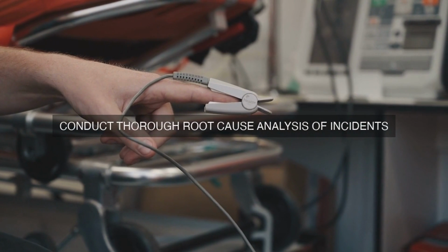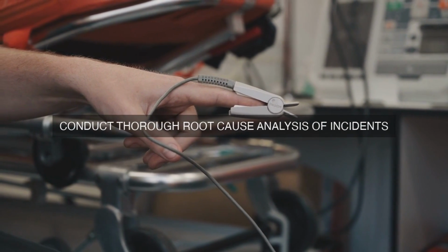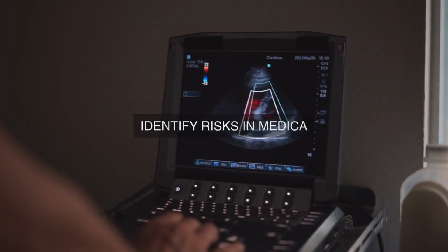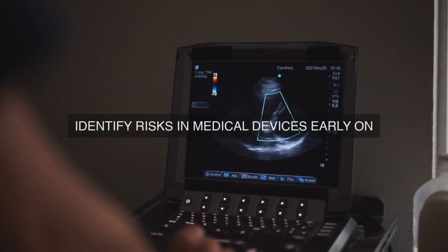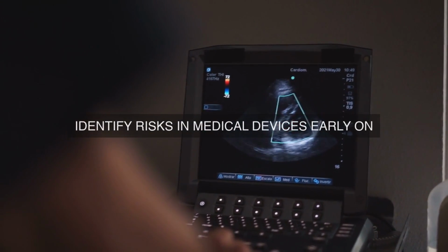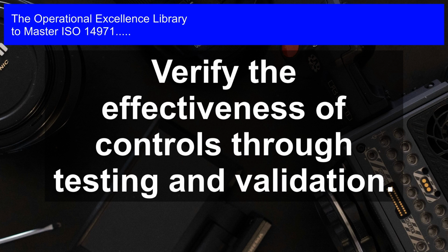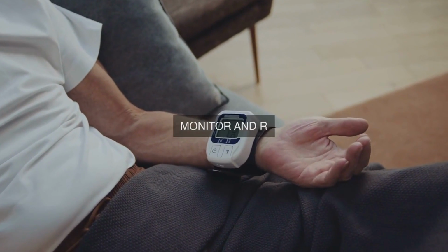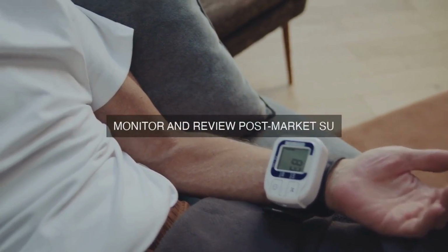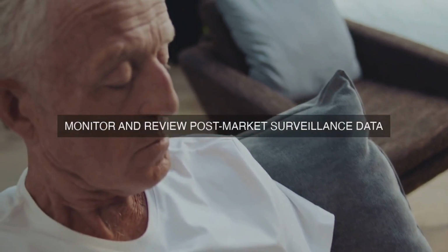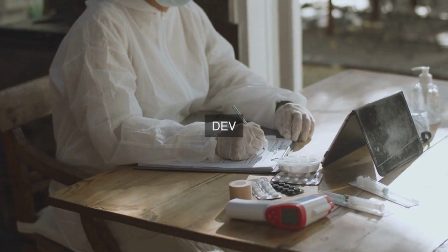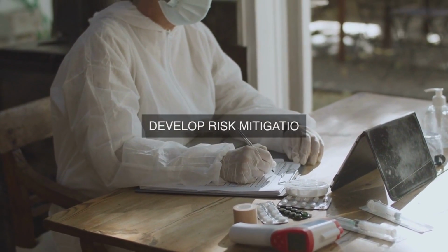ISO 14971 also emphasizes the importance of incorporating human factors into the risk management process. This involves considering the user interface, user instructions, and the environmental factors that could affect the safe use of a medical device. The standard requires manufacturers to maintain a risk management file that documents the entire risk management process, including risk analyses, risk estimations, risk evaluations, risk controls, and risk reviews.